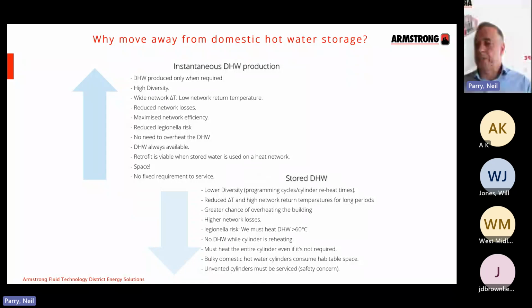Now, I often also hear the comment, well, if I put a cylinder in, I can maybe use a 12 kilowatt coil, whereas if I go instantaneous, I now need 35 kilowatts. So obviously the energy centre is going to be a lot bigger for instantaneous than it would be for stored, and obviously the piping as well. Well, that's an error, I'm afraid, because what you find with instantaneous hot water generation, if you think about running a bath, it may take you 5 minutes to fill the bath. The moment you turn that tap off, if it's instantaneous, the demand stops.